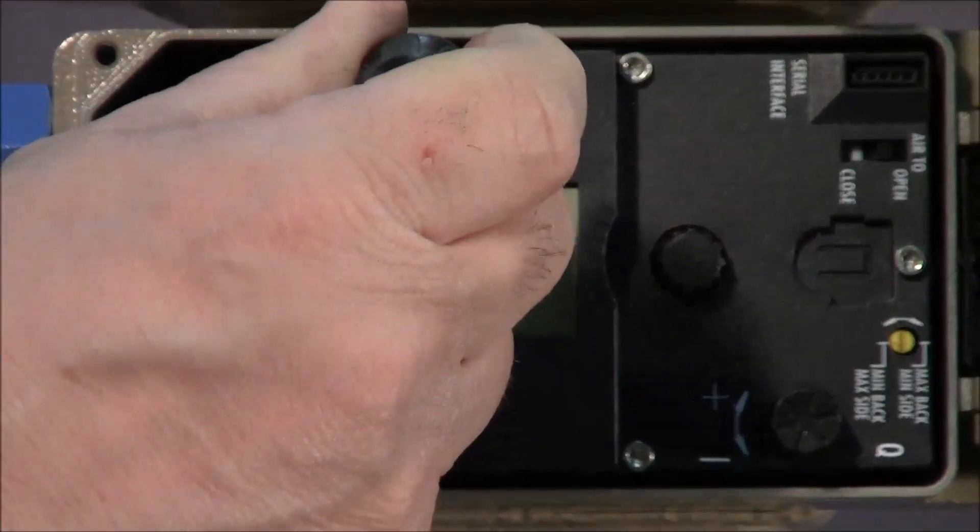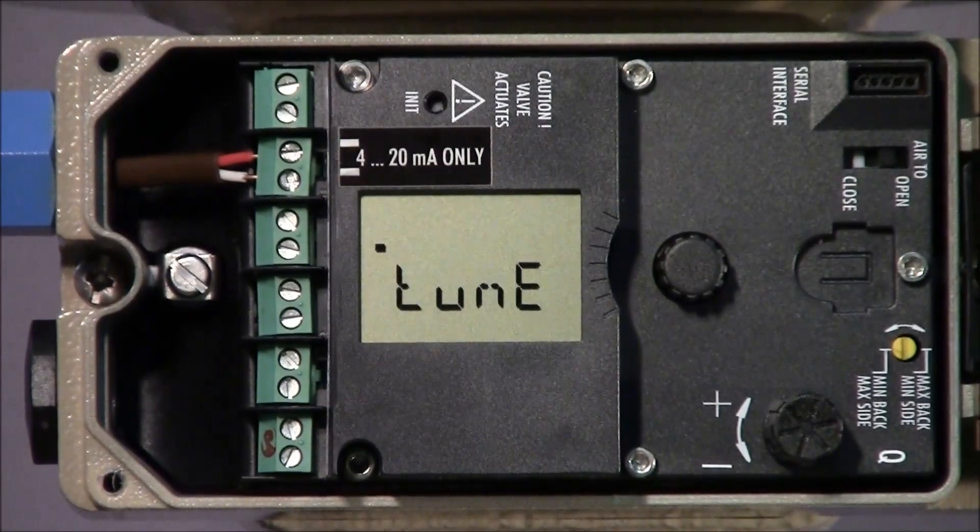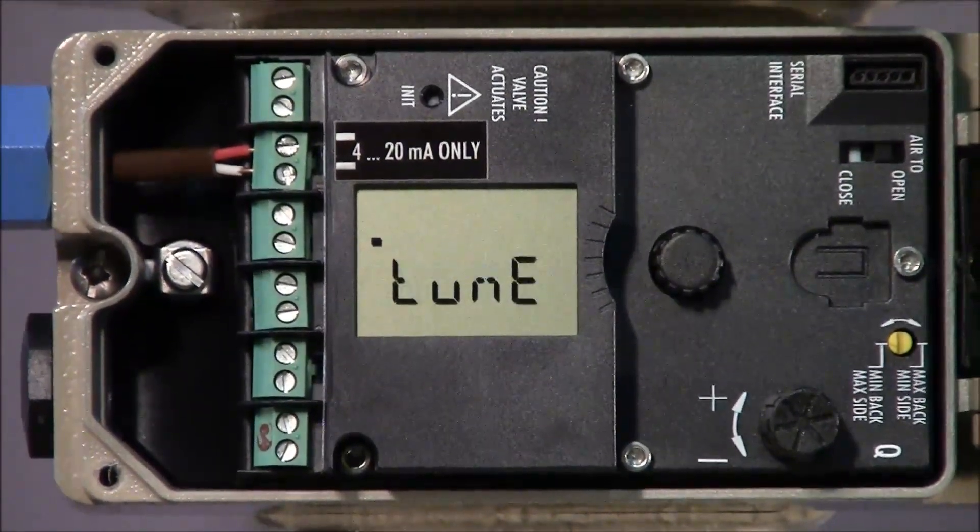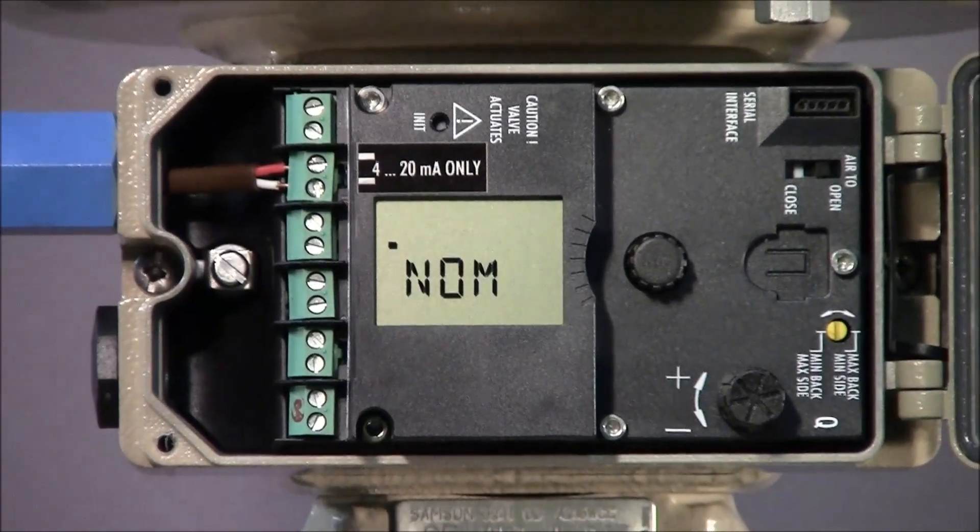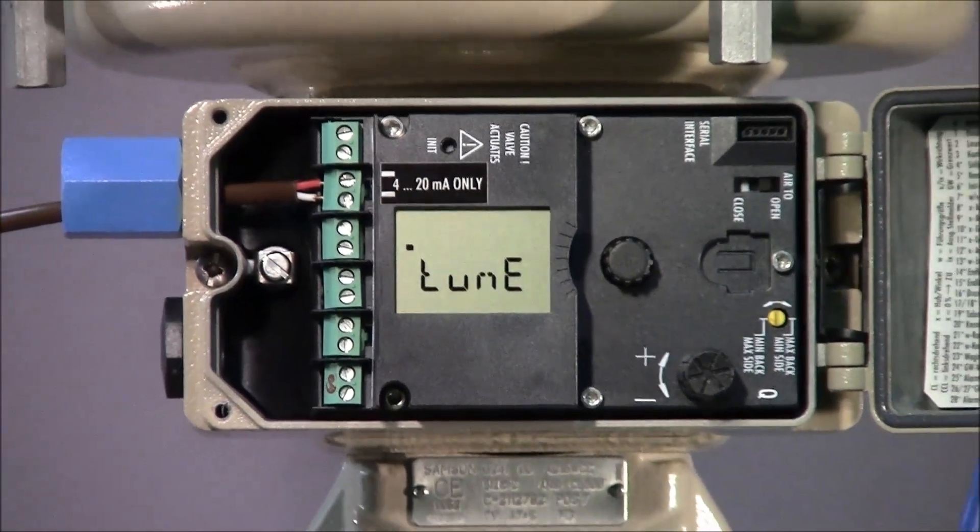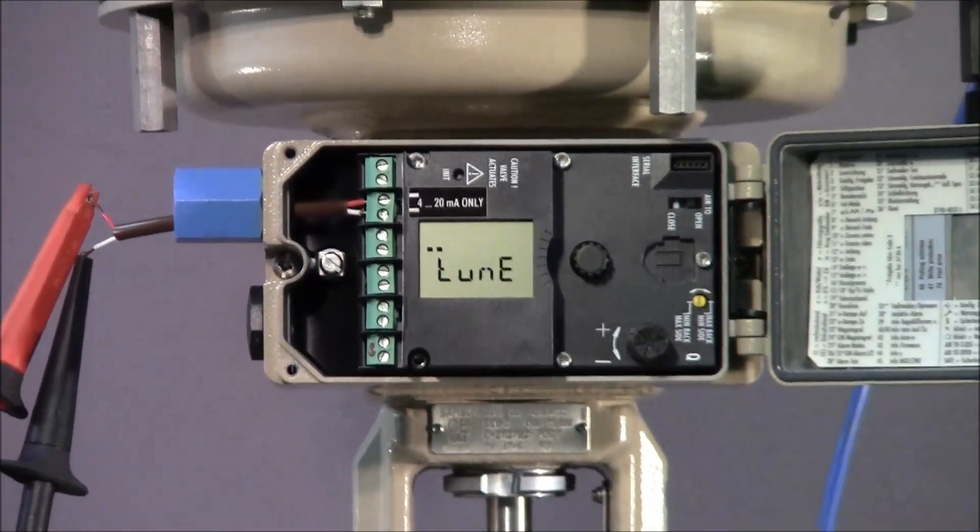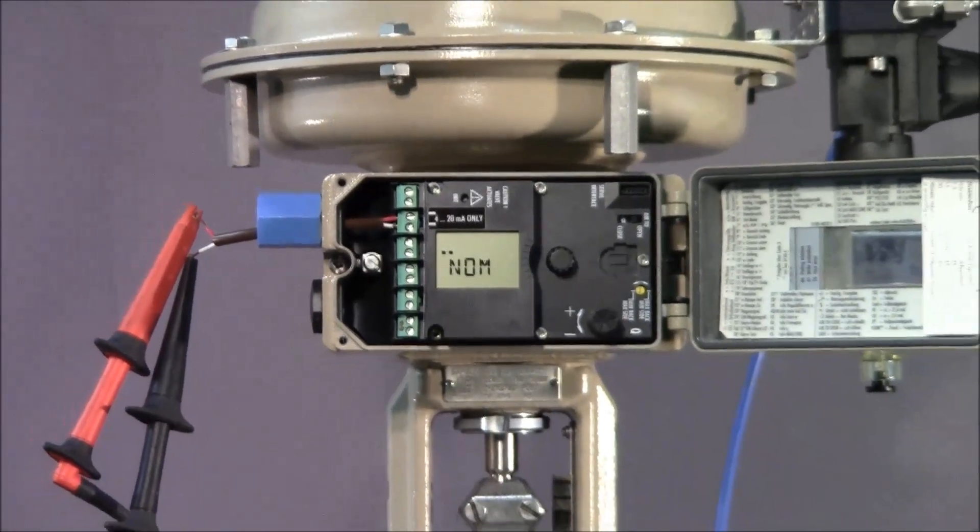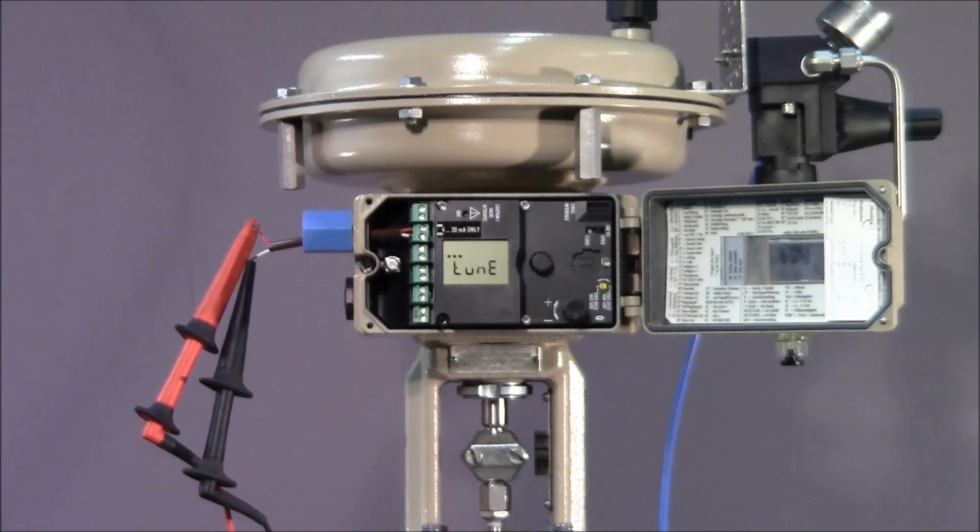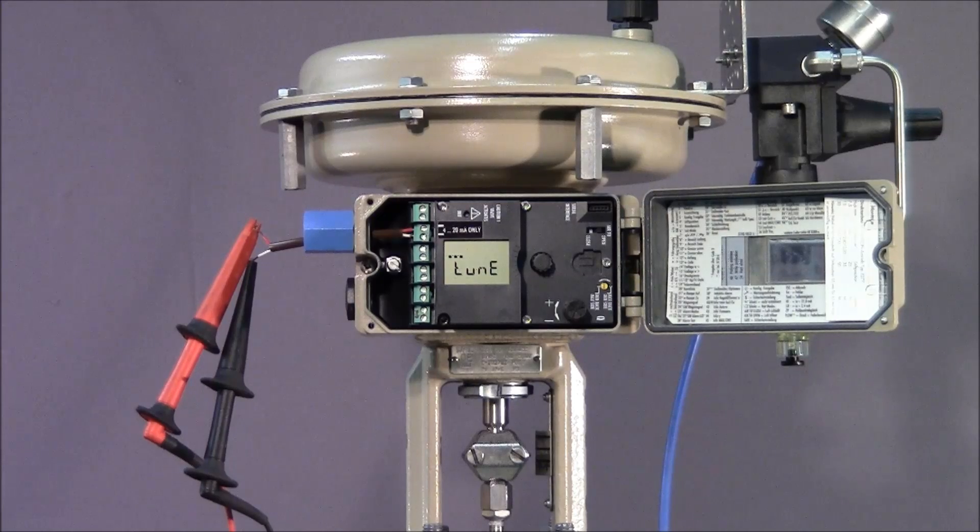We now go back to parameter 0 and press the recessed initialization button to begin the auto calibration process. This process can take a few minutes while the positioner adapts itself to the specific valve and its operating characteristics. It is important not to disturb or interrupt this process until it's finished.